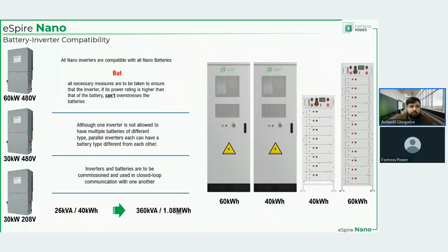And also, when the system is in operation, there must be closed loop communication between the batteries and the inverters. So if the batteries are interconnected, they must be in communication. If batteries and inverters are interconnected to one another, they must have closed loop communication with one another. And if inverters are working in parallel, they must have communication with one another.